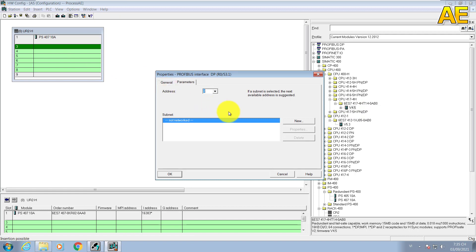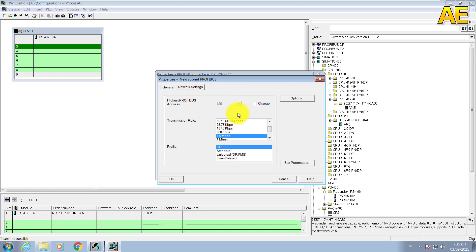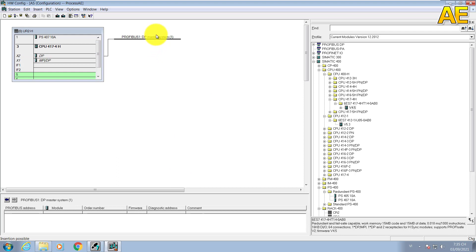And this is the setting for the Profibus network. I will select the network number one. We create new. I will let the name Profibus 1 here. And the subnet ID I will let default. We can change, but in this project I will let default. The network setting here, this is the transmission rate. I will select 1.5 megabit per second here. You can see one DP Master System created.